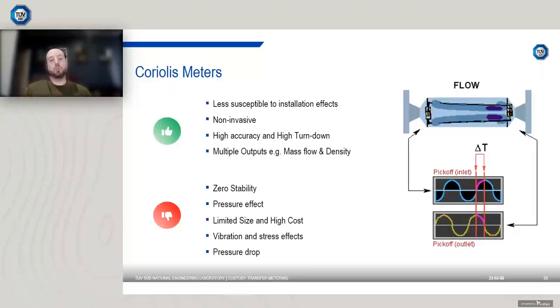So what are the advantages of a Coriolis meter? Well, like I say, they give you multiple outputs, mass flow and density. So mass flow is a big advantage. It can negate the necessity for things like a separate densitometer. They are not susceptible to installation effects. So again, if you know that you're going to have installation effects like bends, T-pieces, valves upstream of the flow measurement device, the Coriolis meter is less affected than turbine meters, orifice plates, for example.